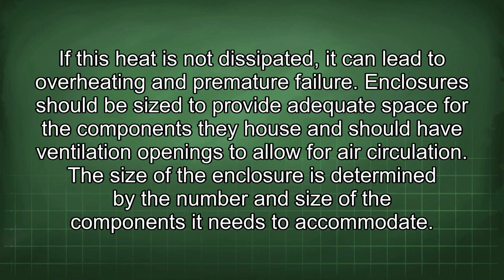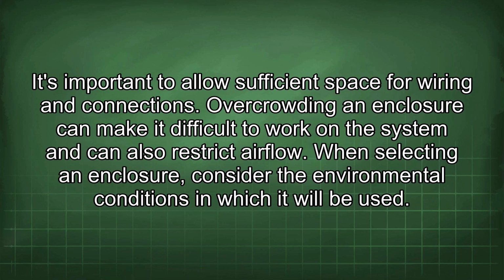Enclosures should be sized to provide adequate space for the components they house and should have ventilation openings to allow for air circulation. The size of the enclosure is determined by the number and size of the components it needs to accommodate. It's important to allow sufficient space for wiring and connections. Overcrowding an enclosure can make it difficult to work on the system and can also restrict airflow.